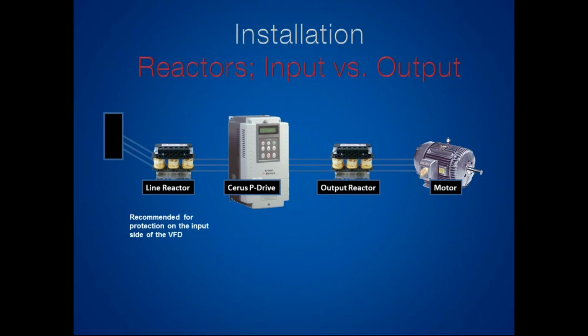That's why we at LinkSpring and at FCS elect to use a 3 or a 5% line reactor on the very front end of the drive so that we ensure that the entire drive is protected, not just the back half. Okay? Go ahead and go to the next slide.